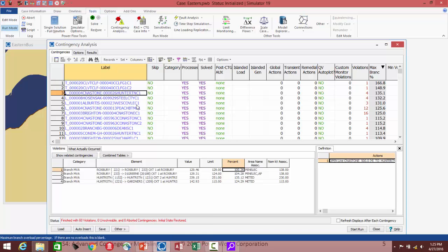But certainly if you're doing something like running a security constrained optimal power flow, which we'll take a look at in a later section, where you're asking the program to relieve the base case and all the contingent violations, you don't want it to dispatch generation around contingent outages that aren't really problems because of remedial action schemes. So one way you could accomplish that is you could just tell it to ignore certain overloads for certain contingencies.